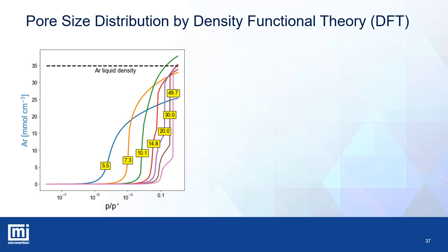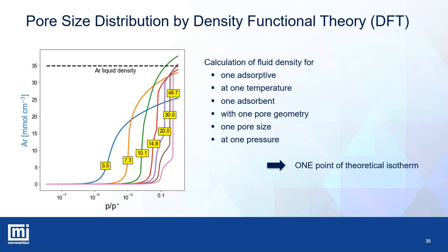Using density functional theory (DFT), a molecular-based statistical thermodynamics approach, to create models for pore size calculations has become a well-established approach. The theory is used to model the properties of the adsorptive fluid confined within the pores by calculating density profiles reflecting the behavior of the adsorbate at different pressures. These values generate a set of theoretical isotherms — the DFT kernel or DFT model — where each theoretical isotherm represents one pore size. In practice, the fluid density is calculated for one adsorptive, at one temperature, for one specific material, with a defined pore geometry, one pore size, and at one pressure. Creating these kernels takes a lot of computation time.